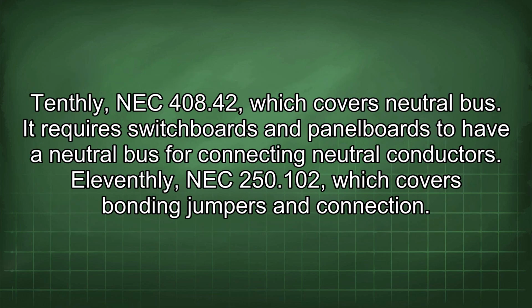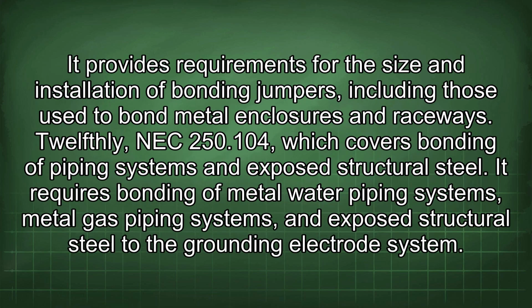Tenthly, NEC 408.42, which covers neutral bus. It requires switchboards and panel boards to have a neutral bus for connecting neutral conductors. 11thly, NEC 250.102, which covers bonding jumpers and connection. It provides requirements for the size and installation of bonding jumpers, including those used to bond metal enclosures and raceways.